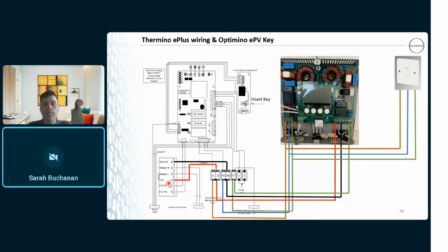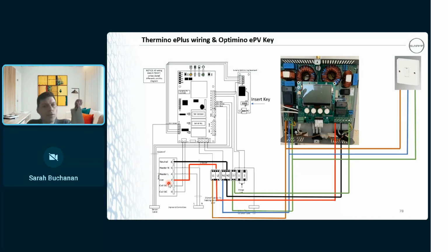Okay, so John, who's asked that question, has just said, we're doing the timer via a smart relay which supplies 230 volts to the coil of an additional relay in the eddy, which provides the no volt contacts. Is that the relay sensor board? I'll just see if John can put that in the chat. Yeah, it'll just be a different way. This is the basic configuration. Your relay sensor board will go up here, which has got the relay 1, relay 2, I think the EcoSense connections as well. John says yes, that is a relay sensor board. Yeah, so it's just a different way. So you would wire that.